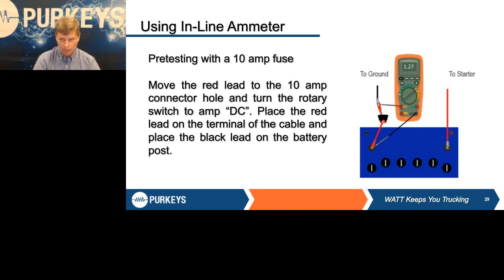But think about this—connected in parallel with that fuse holder, what would my meter display if I had a 2.5 amp load on right now? I'll give you a second to think about it. If you look at the meter displayed there, it tells you the answer: basically, it would be half.